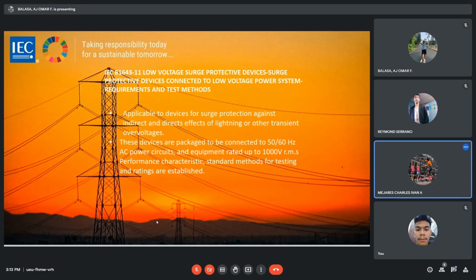IEC 61643-11, low voltage surge protective devices connected to low voltage power systems, requirements and test methods. Applicable to devices for surge protection against indirect or direct effects of lightning or other transient overvoltage. These devices are packaged to be connected to 50 or 60 Hz AC power circuits and equipment rated up to 1000 volts RMS. Performance characteristics, standard methods for testing and rating are established. These devices contain at least one nonlinear component and are intended to limit surge voltages and divert surge currents. Next.